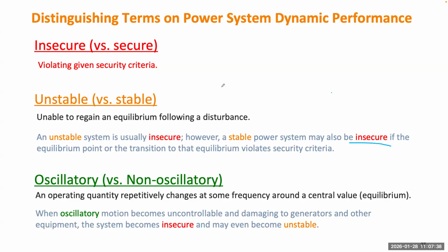When oscillatory motion becomes uncontrollable and damaging to generators and other equipment, the system becomes insecure and may even become unstable. This means the oscillatory phenomenon is not the end of the world. If the oscillatory behavior can be mitigated and doesn't cause any instability or violation of standards, it may be fine. Operators don't like oscillation, but it may not be really bad. It at least indicates the generator is recovering to a new equilibrium.